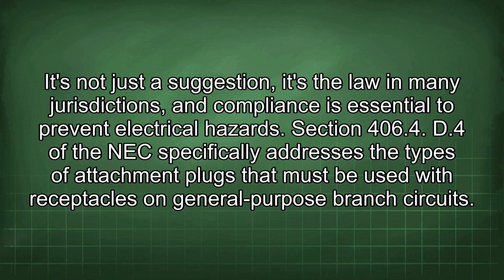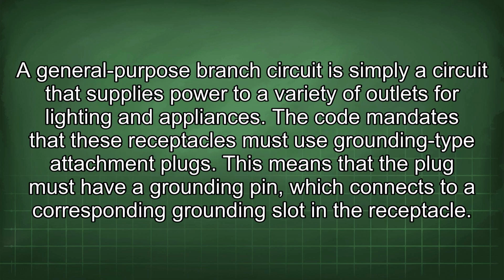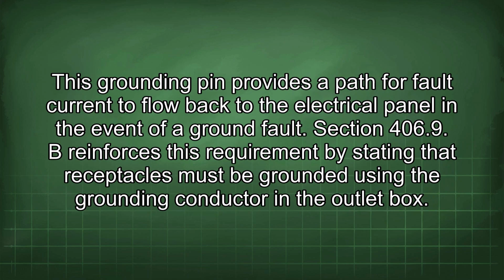Section 406.4 D4 of the NEC specifically addresses the types of attachment plugs that must be used with receptacles on general-purpose branch circuits. A general-purpose branch circuit is simply a circuit that supplies power to a variety of outlets for lighting and appliances. The code mandates that these receptacles must use grounding-type attachment plugs. This means that the plug must have a grounding pin which connects to a corresponding grounding slot in the receptacle. This grounding pin provides a path for fault current to flow back to the electrical panel in the event of a ground fault.